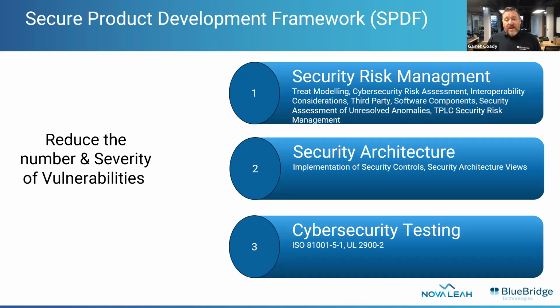The UL standard and the ISO standard really give good guidance on how you will test for malware, malformed input, structured pen tests, software weaknesses, static code analysis, and static binary analysis. So it's a really good template that you can use to overlay on your existing quality management system. On to the next slide, Joe.